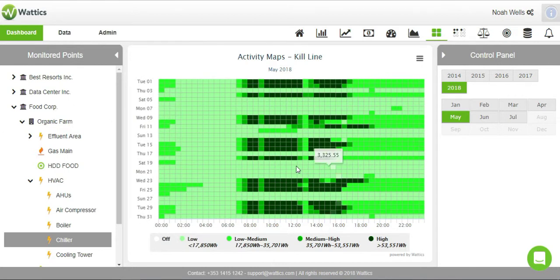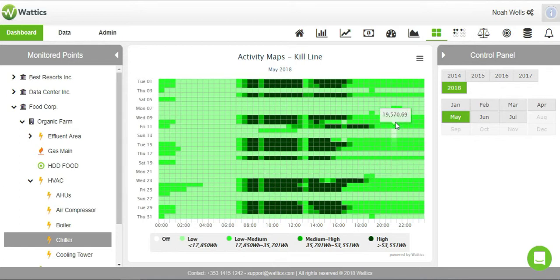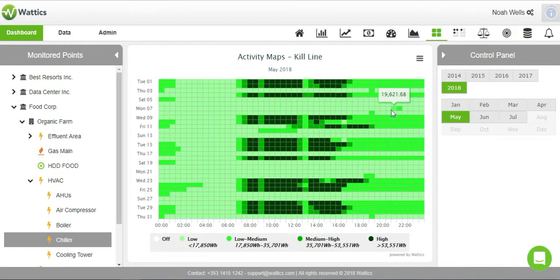The high intensity is centered around standard work hours, but the activity map clearly shows that the chiller is never fully shut down. For some appliances, you can see a pattern like this and the activity maps makes it easy to tell if there was a mistake or failure, such as if it was left on during the night.